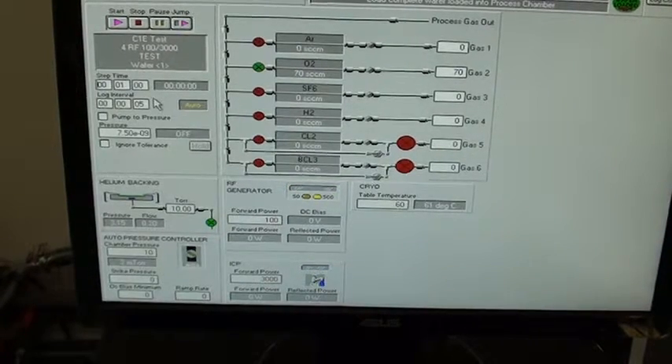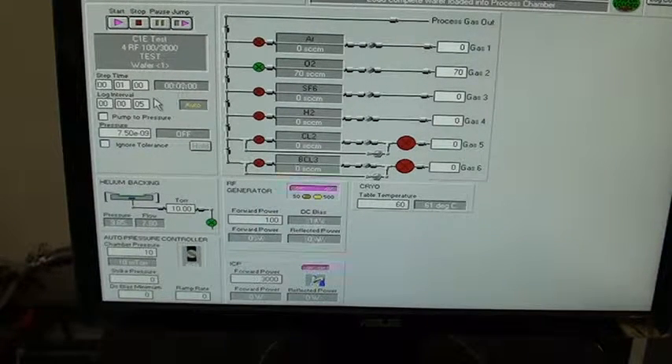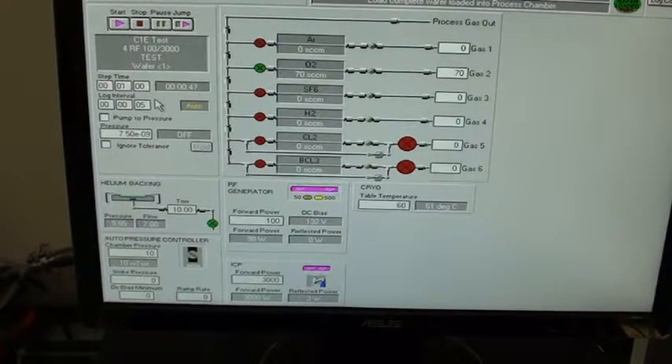We've changed into our next power step. This one's going to set a new pressure: 10 torr backside pressure, 10 millitorr chamber pressure, and 100/3000 watts for RF powers. Gas flow set point changed to 70 SCCM. You can see it tuned in very well.